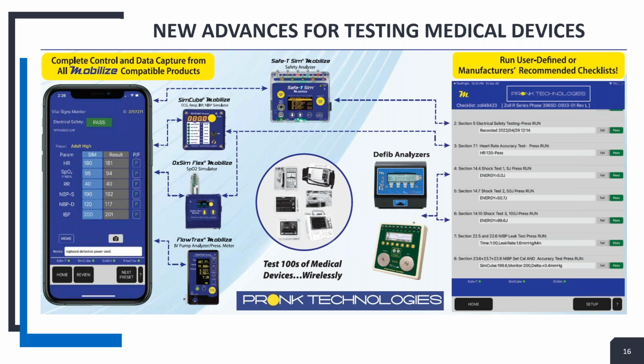So it wants us to do a shock test of 5 joules. You're going to want to hit the run button there. It will tell the defib analyzer to go into measurement mode for discharge. It's set for 5, and then we're going to go ahead and charge it, and once it's set, fire it. In that gray box down below, you'll be able to see the result from the analyzer for that discharge test. So what was the joule that it measured?